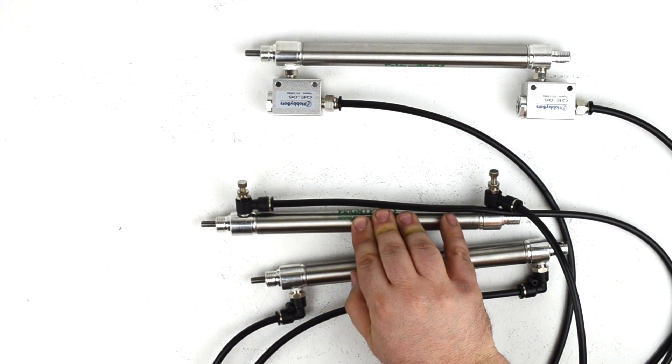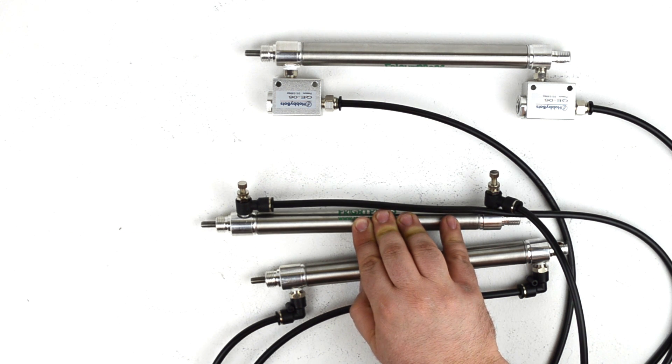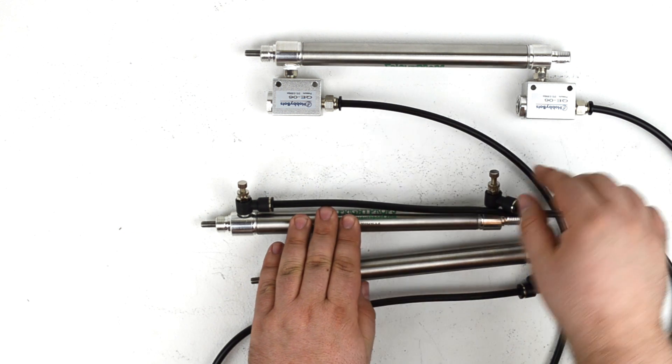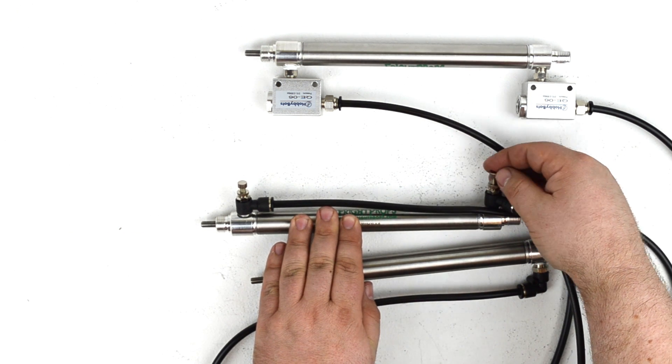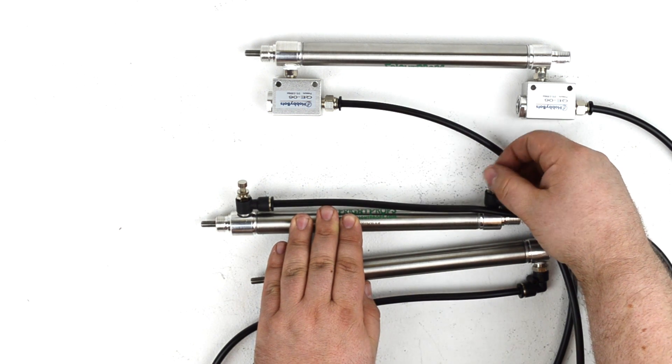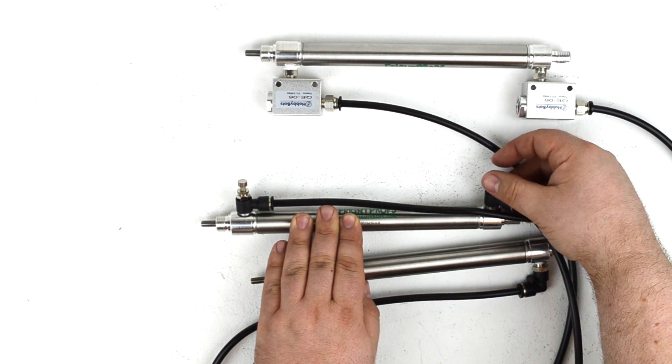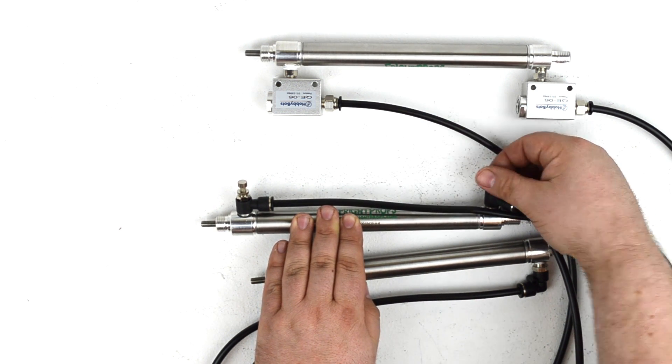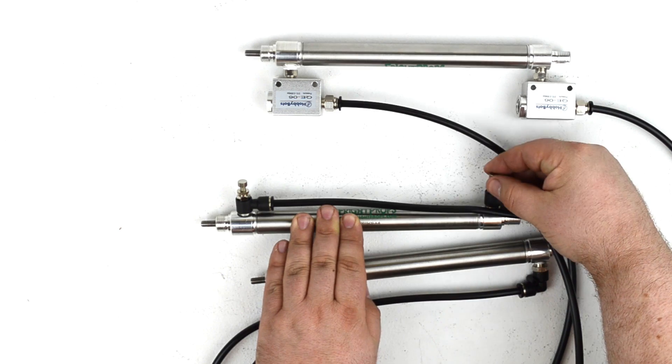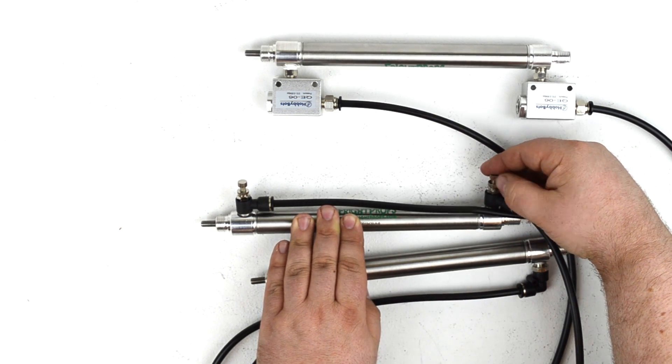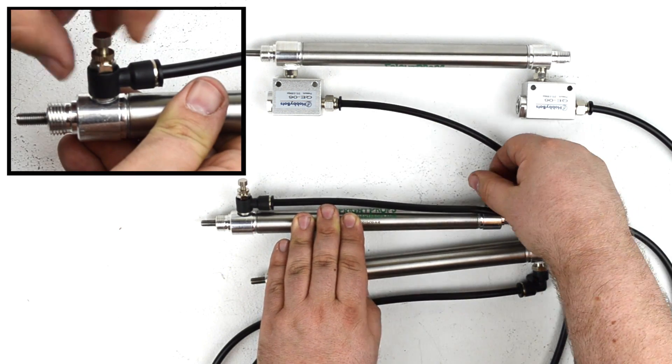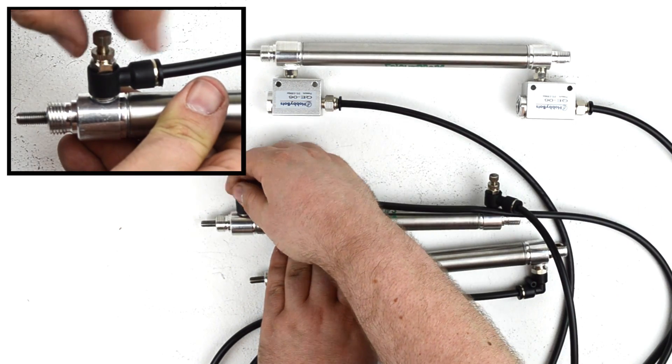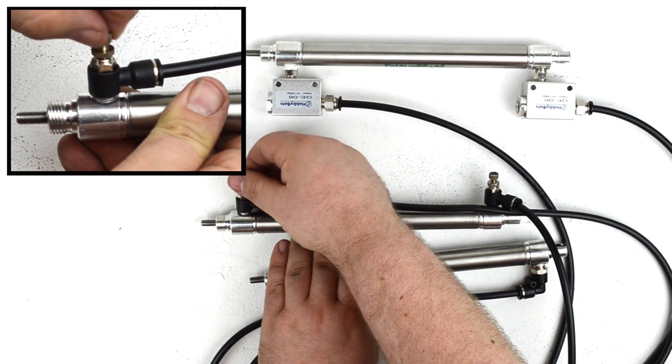So if you wanted your cylinder to extend slowly and retract more quickly, you could do that using these flow controls. Or if you wanted it to extend quickly and retract more slowly, you would simply tighten the needle dial on the rear cylinder port and open it up at the front.